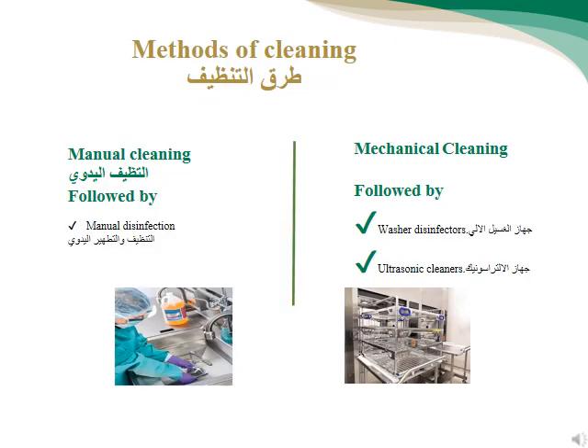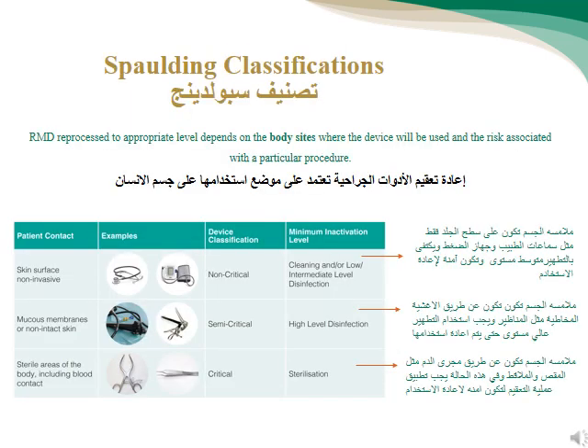Methods of cleaning: Manual cleaning followed by manual disinfection, or mechanical cleaning followed by washer disinfector or ultrasonic cleaner. Spaulding Classification — reusable medical devices are reprocessed to an appropriate level depending on the body site and risk of the procedure. If the device contacts the patient's skin only, it is considered non-critical, and low-to-intermediate level disinfectants are sufficient after cleaning.